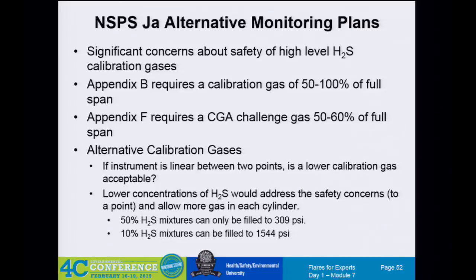sulfur concentration. So what if you have an acid gas flaring event and you could get maybe up to 80%, 90% H2S in your flare gas? Now you have to have an instrument that spans basically up to 100% H2S. So now you have to be bringing in a cylinder of gas. We're wearing these monitors that will alarm at 5 ppm, and then you've got to bring in a cylinder that could be 50% H2S. The safety issues around this are tremendous, and everybody should spend a lot of time thinking about this.